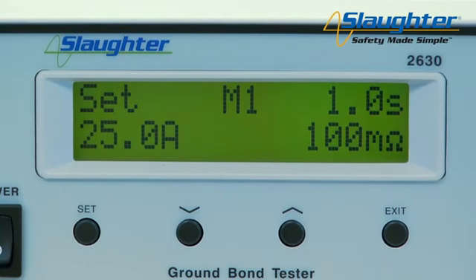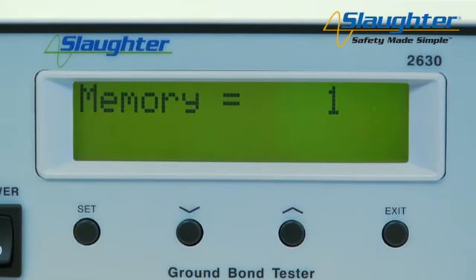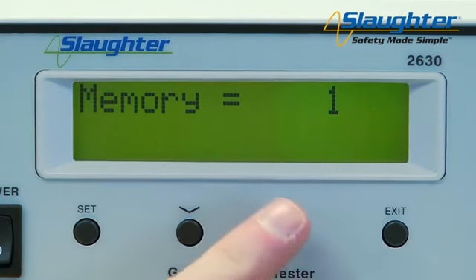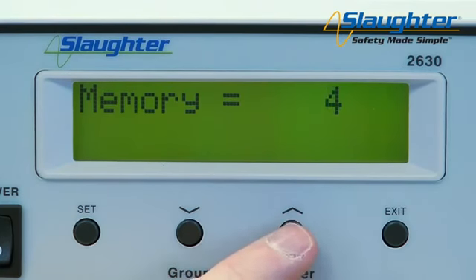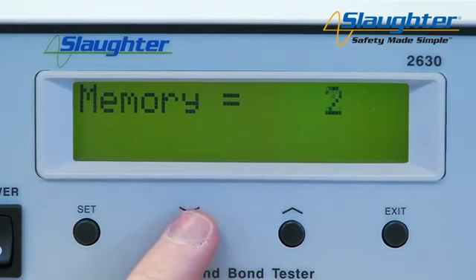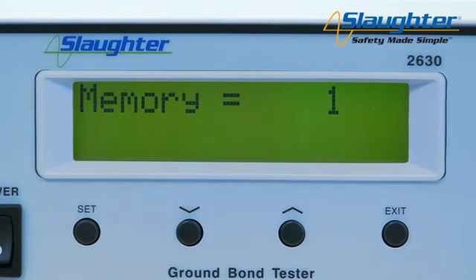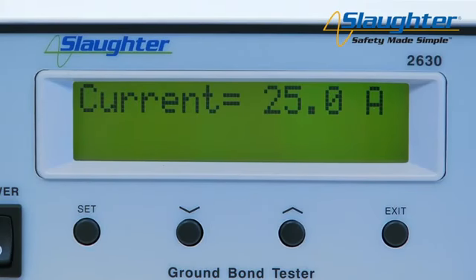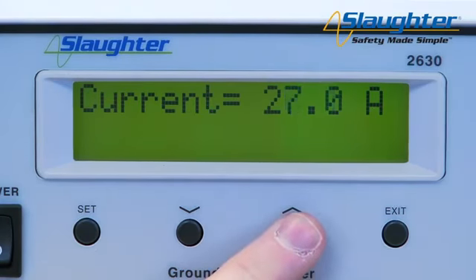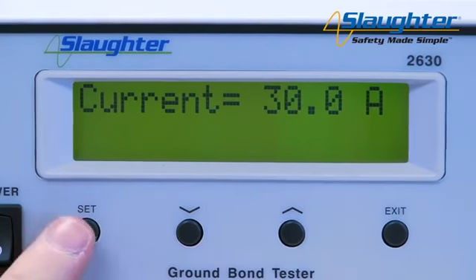First, we're going to set up an AC ground bond test. From the main screen, press the Set key. You will now see the memory parameter on the display. This indicates that you are now editing the memory parameter. Use the up and down arrow keys to select the memory number for the test. You can set this value anywhere from 1 to 5. This allows you to set up to 5 separate ground bond tests on your 2600 series tester. When your memory has been selected, press the Set key again to navigate to the next parameter. Use the up and down arrow keys to change your parameter values and the Set key to accept and navigate to the next parameter.